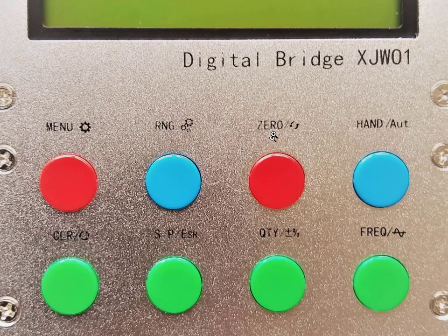So the next button we have here is marked as 0. This is for setting the compensation of your probes. So what you do is, first of all, you disconnect the two probes from each other so they're not shorted together, and plug all 4 wires into the box. Make sure you have the connections the right way around, so the left probe goes in the 2 left-hand sockets and the right probe goes in the 2 right-hand sockets. Doesn't matter which way around they are. And then with them open, you press the 0 button.